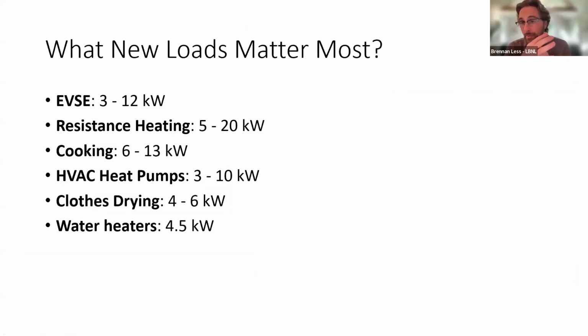The loads that matter most, it depends, but the rated power of these kinds of loads does vary a lot. EVSE can be really huge - in a lot of cases we start seeing 12 kilowatt EVSE chargers put in place. Resistance space heating or tankless electric water heating can be really big, anywhere in the 5 to 20 kW range. 20 kW is almost the entire capacity of a 100-amp panel - let's remember that. Cooking can vary, but most electric ranges we're installing are in that sort of 12 kW range.